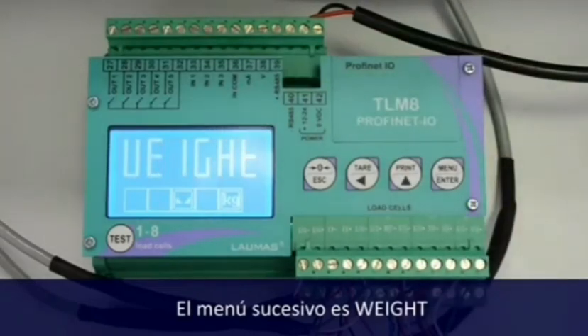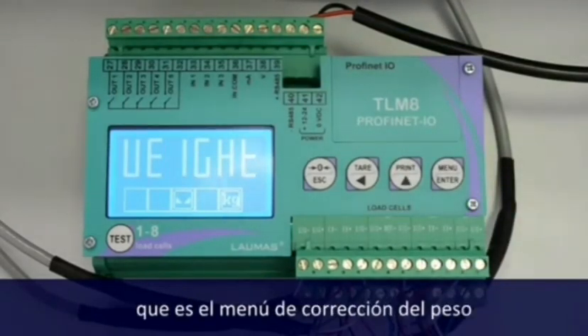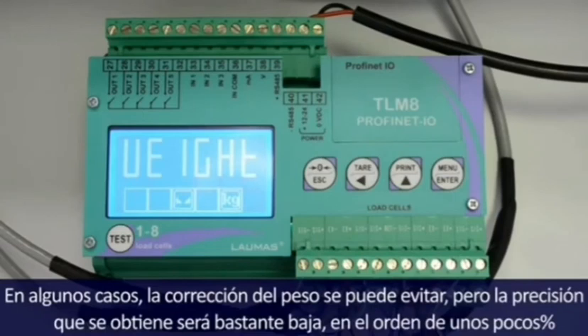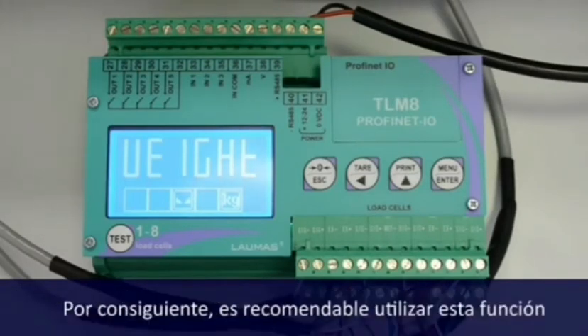The next important menu is weight. This is the weight correction menu. In some cases you could avoid it, but the accuracy you will get will be quite low, in the order of some percent. So you normally should do it.